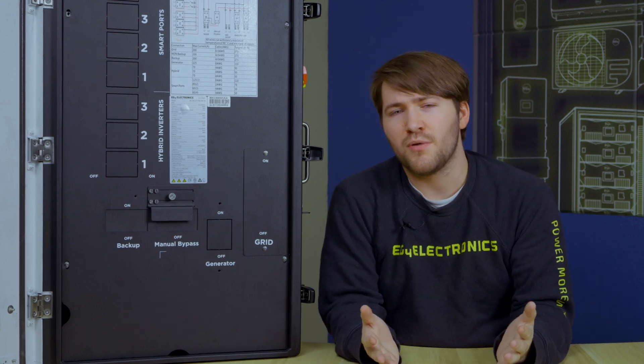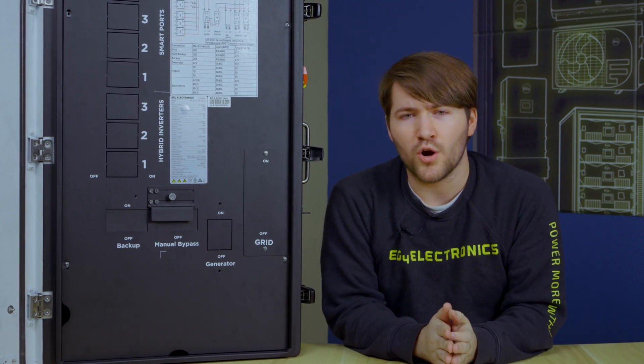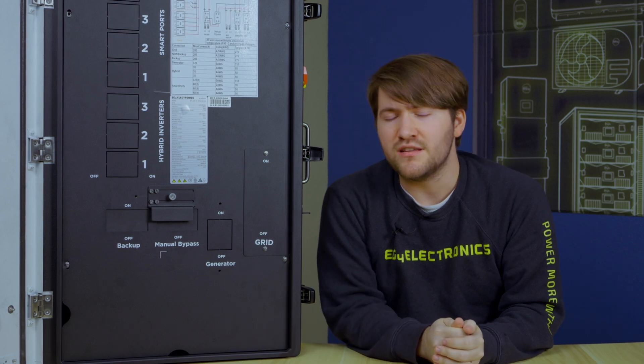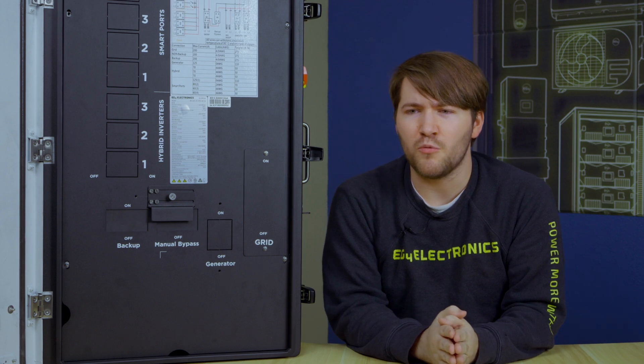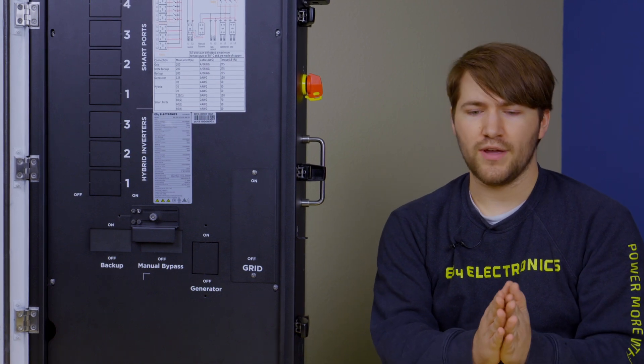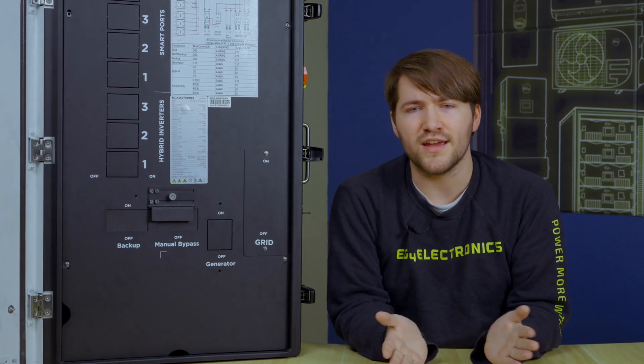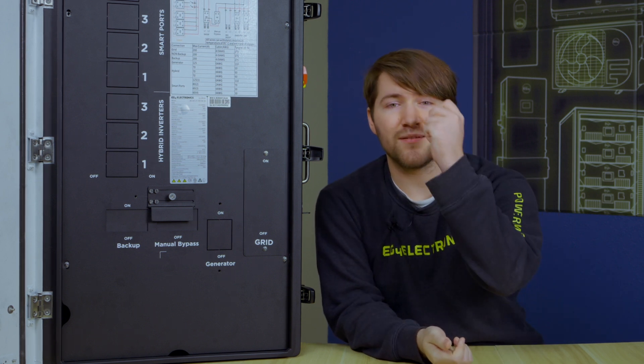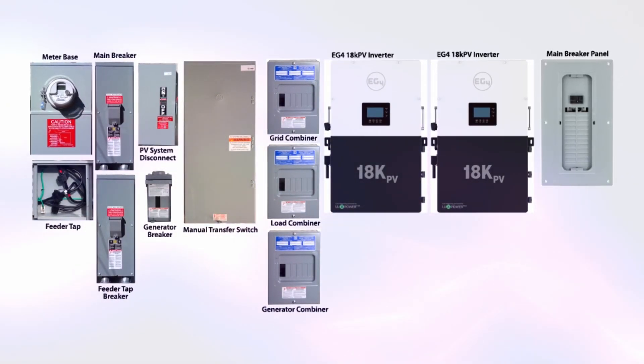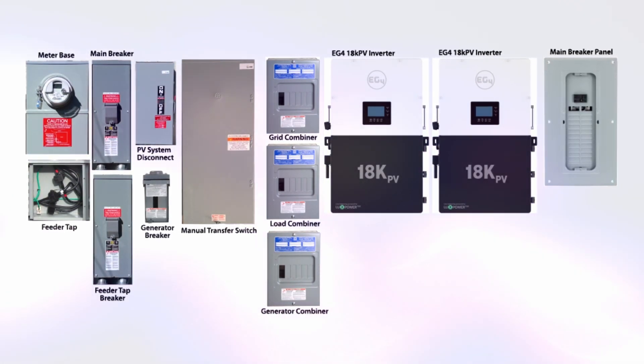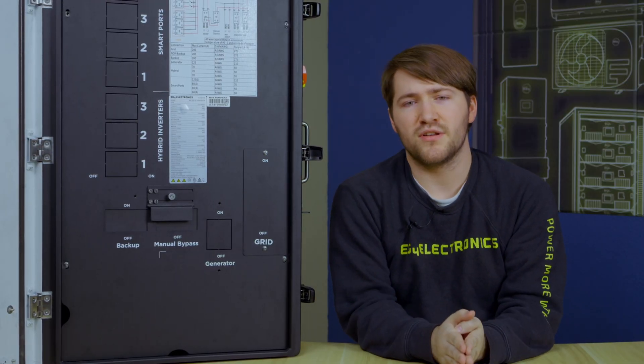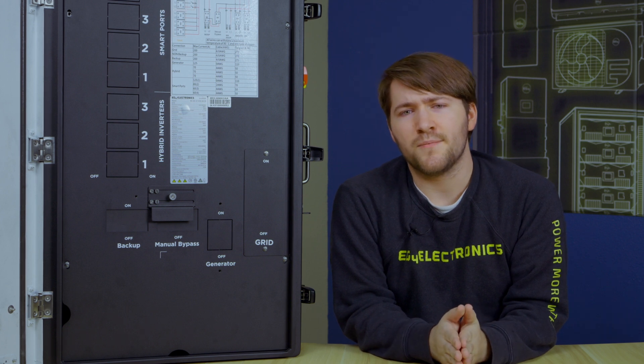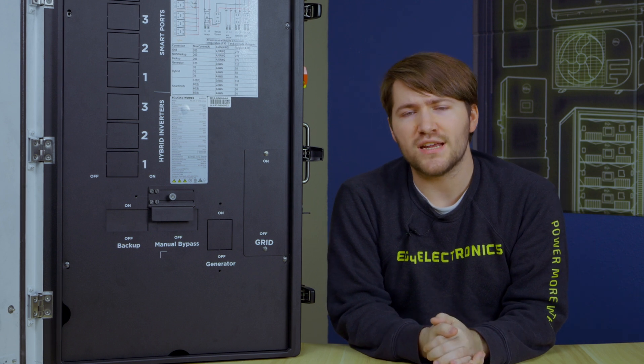So the grid boss has all of these neat features that were either pieces of the all-in-one architecture or pieces of what you would need to do to install an existing system. But let's take a moment to kind of see what this would look like on a realistic stage. When you're implementing, say for example, a two hybrid inverter system with a generator integration, you may end up with a wall that looks something like this. There are 11 boxes on this wall that all have various functions, whether it be a breaker, or a splitter, or a combiner. There are a lot of different components working here. So when you slot in a grid boss to the system, what exactly is being affected? What's being removed, replaced, or exchanged?